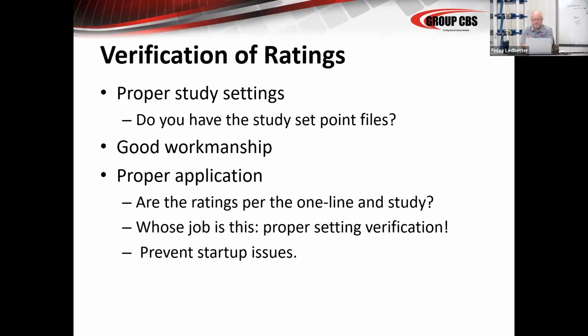Look for good workmanship. Those are the eyes you've got, use them. Smell for bad smells. You can smell ozone, you can smell burning, and when you're testing the equipment, look for smoke. Don't make smoke in the testing business is normally a good rule to live by. Make sure everything's properly applied. Do you have those ratings? Does someone have those settings? The manufacturer should have them. Someone should be making sure that all the ratings are correct per the one line, per the study, per the breaker schedule that gives you all that.